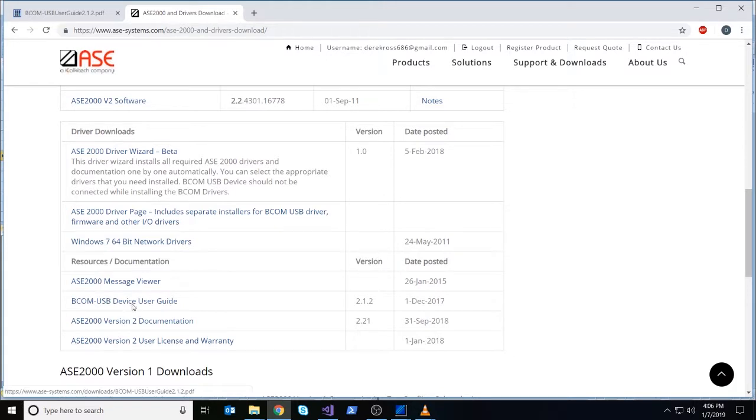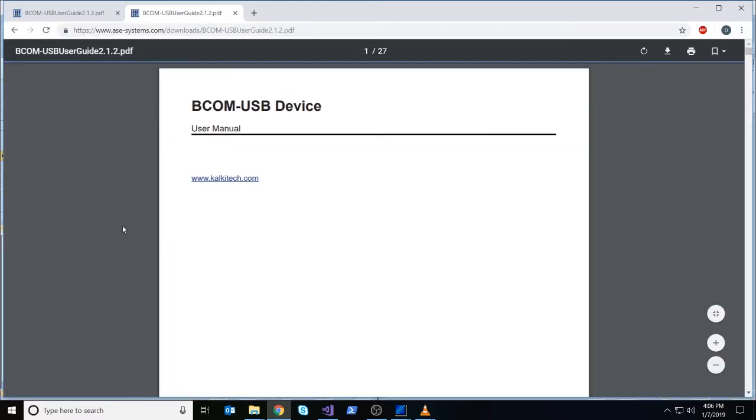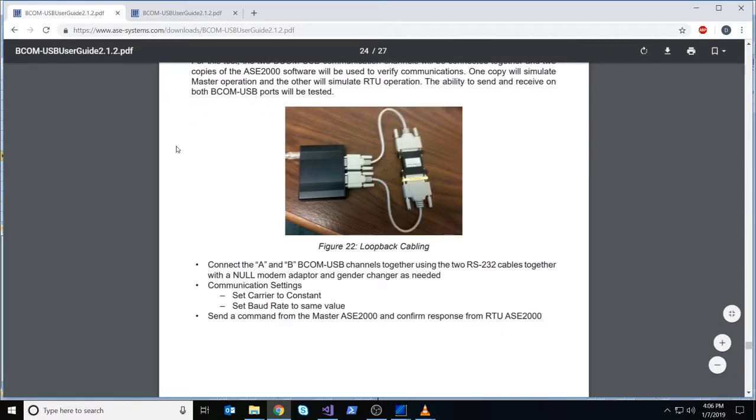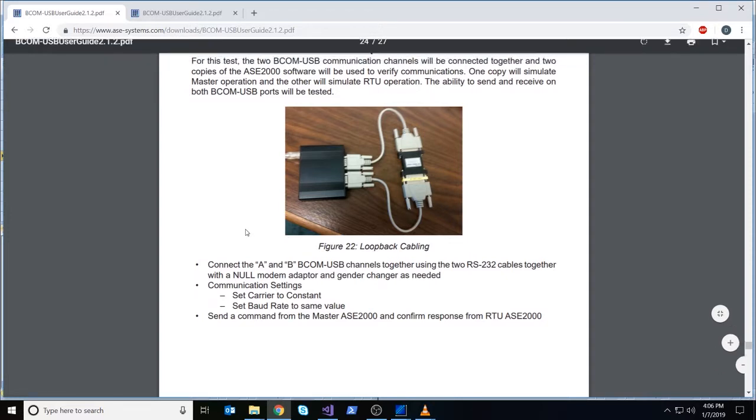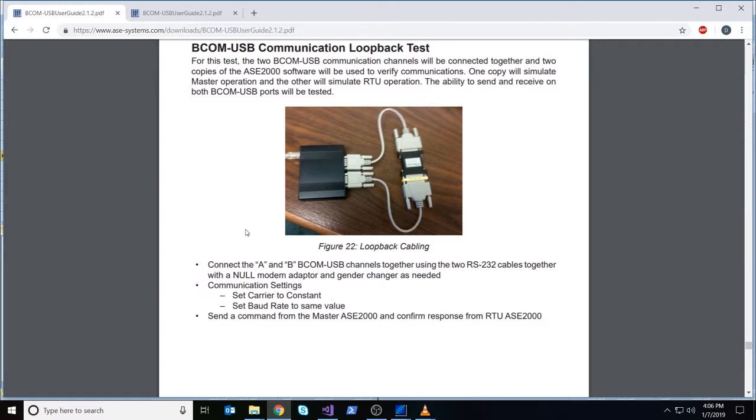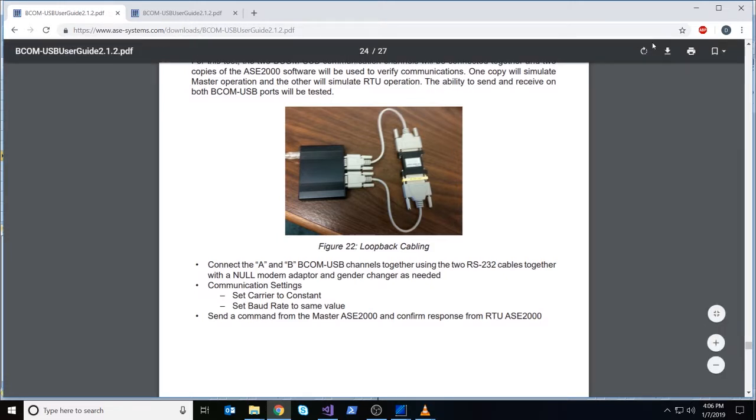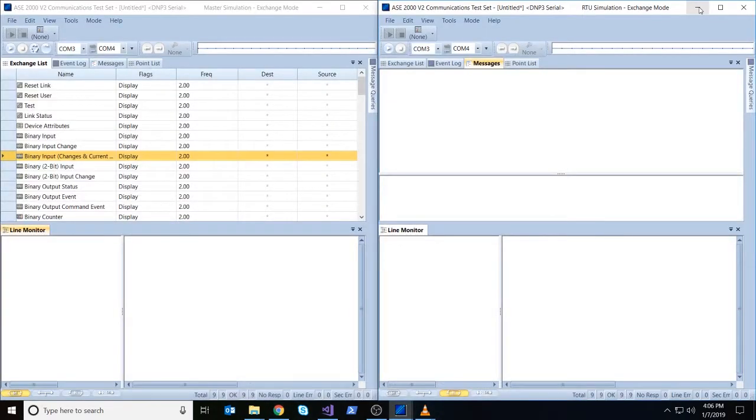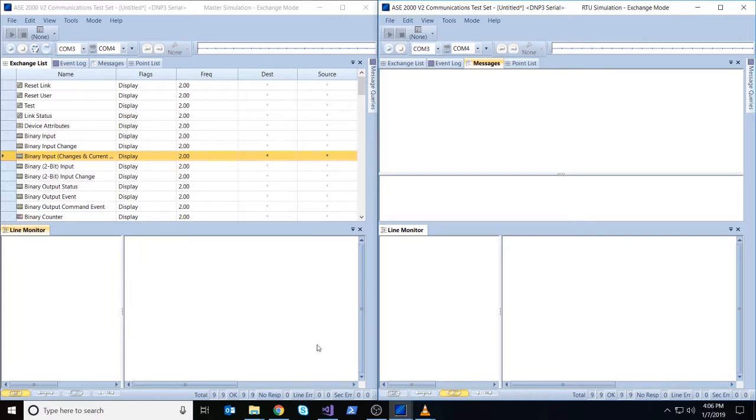If you go to tools and properties on each one of your instances of ASE2000 version 2, go to the communication tab and just make sure your line properties are the same on each side. We've switched to 1200 baud rate, and I'm just going to do a quick check here and make sure that it is the same on here. Switch to 1200, that's good.